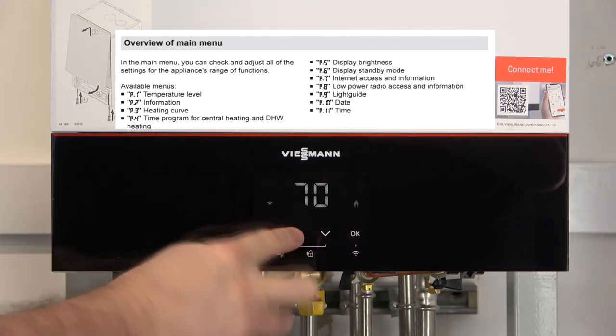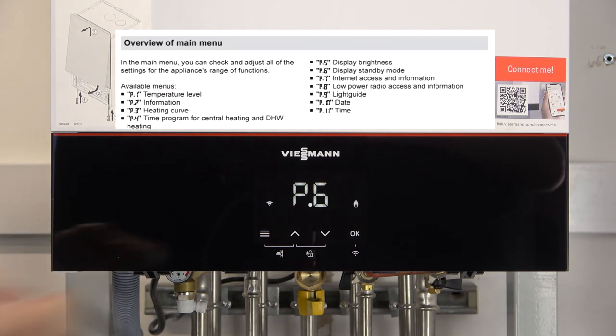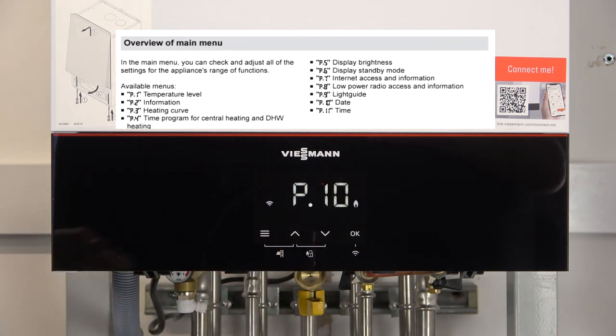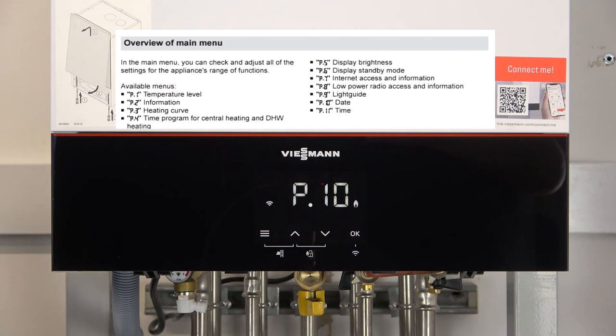We go back into P-5, into display brightness, and put it back up to 100%. P-6 is display standby mode, P-7 is internet access, and P-8 is low power radio access and information. We can also go into P-10 and P-11 which is for setting the date and time. When you first do your commissioning you can set the date and time then, but the only other way to get back into setting them is via P-10 and P-11, and the customer can do this too since this is a customer-focused menu.